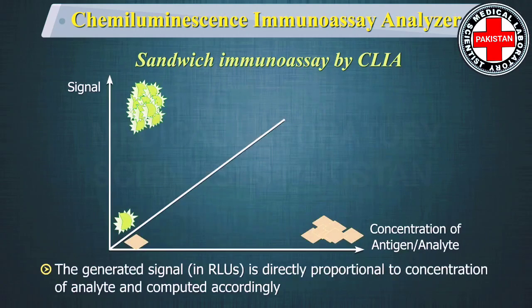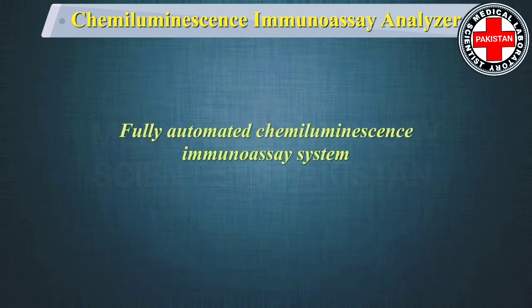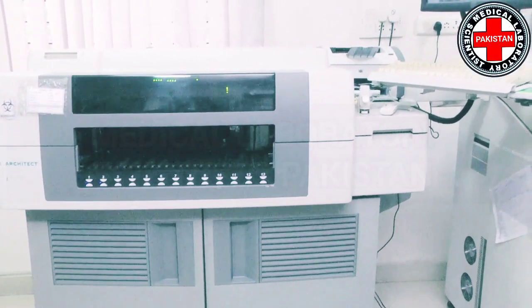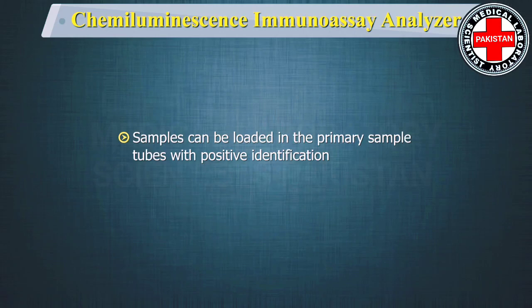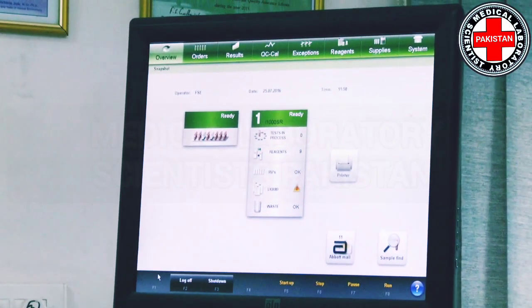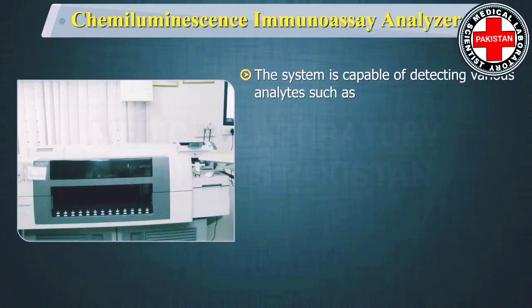The generated signal in RLUs is directly proportional to the concentration of analyte and is computed accordingly. Fully automated equipment usually has a high throughput of about 100 tests per hour and has a walk-away feature. Samples can be loaded in the primary sample tubes with positive identification. These analyzers are computer controlled and can easily be connected to the lab information system for increased data management capabilities.